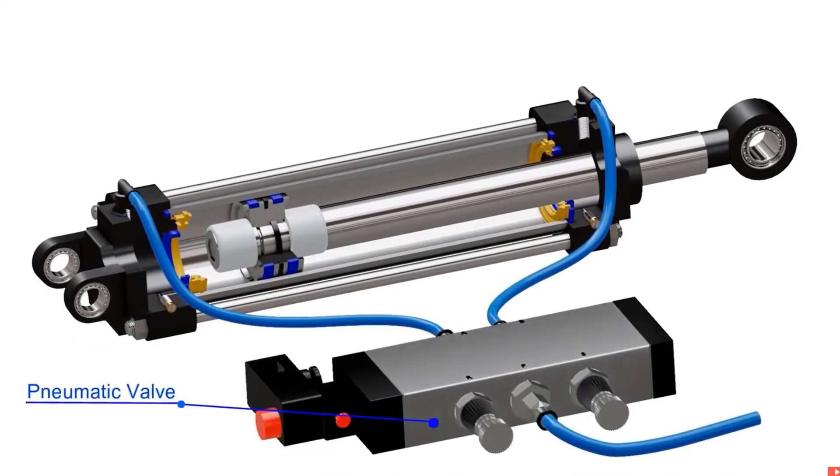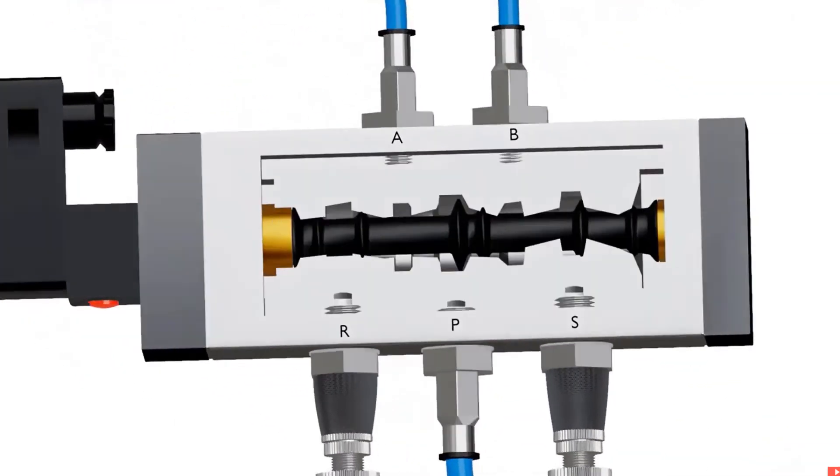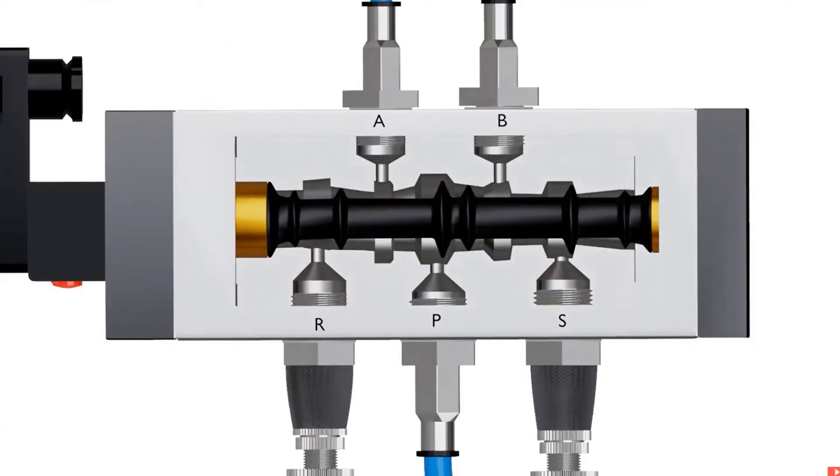A pneumatic valve is connected to these air ports using pneumatic hoses. The valve shown here is a five port, four-way valve. The ports A and B are connected to the cylinder. Port P is connected to the compressed air supply unit. Ports R and S are exhaust ports to which the pneumatic mufflers are attached.